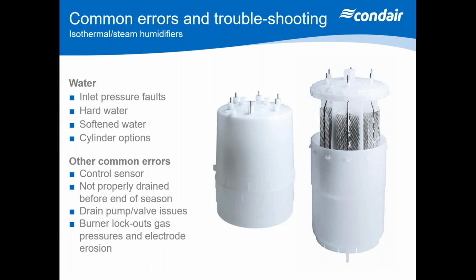Also, as I said about Scotland, you've got options for cylinders. Some of the manufacturers will give you cylinders that go down to less than 100 microsiemens. So if you've got issues with your water on sites in Scotland, there may be a different cylinder out there that might help you get control. Control sensors, as we said, about being in the wrong position.